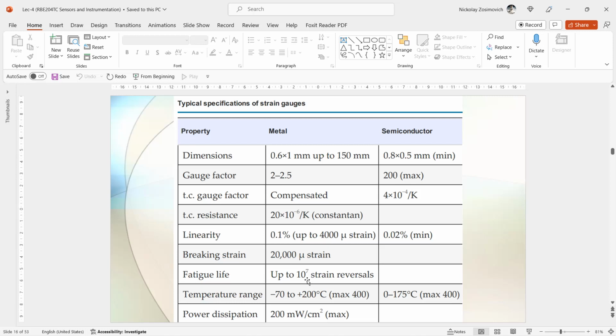Strain gauges have an intrinsic bandwidth of over 1 MHz. So, the system bandwidth depends mainly on the mechanical interface and readout electronics. The resistance of a strain gauge changes not only with stress, but also with temperature. Two parameters are important: the temperature coefficient of the resistivity and the thermal expansion coefficient.